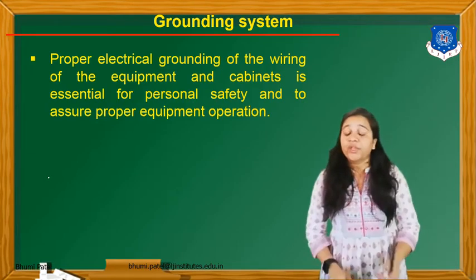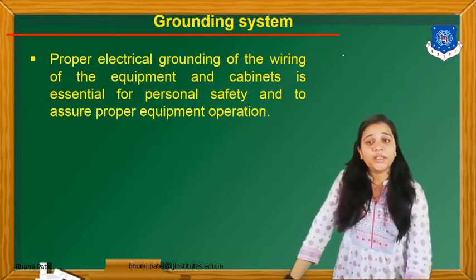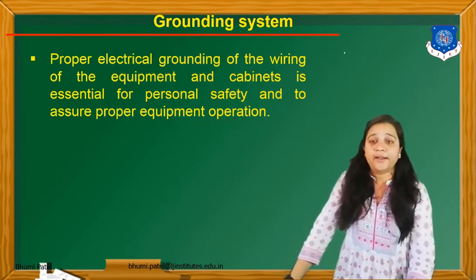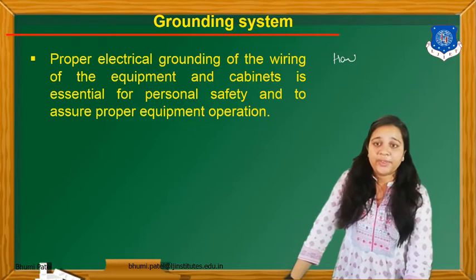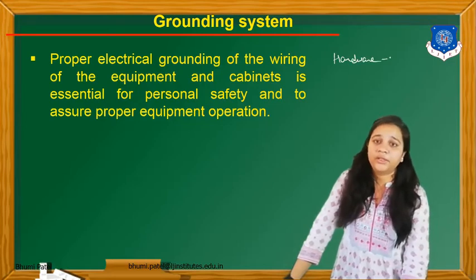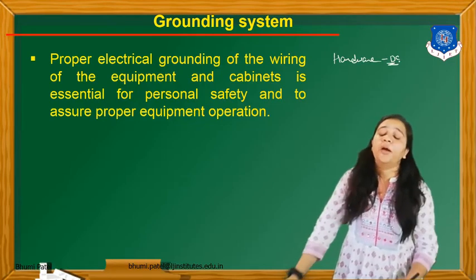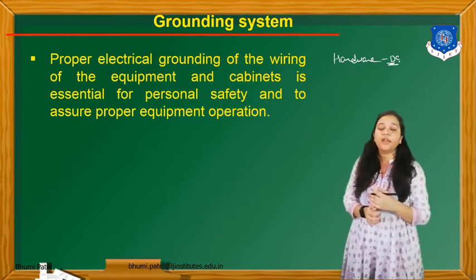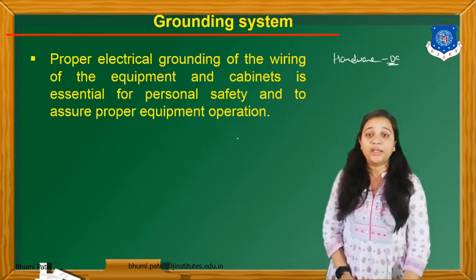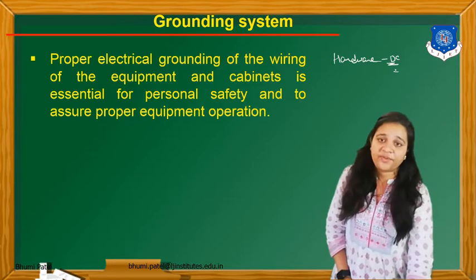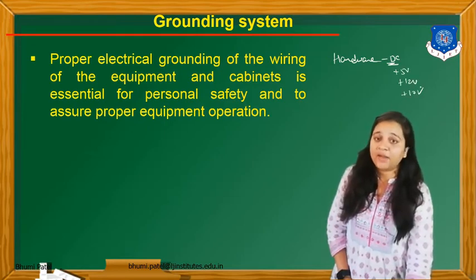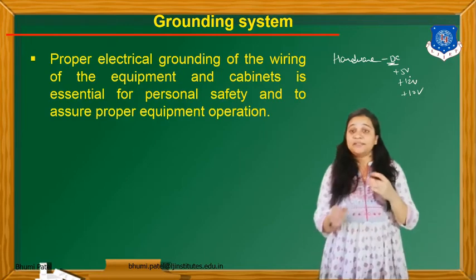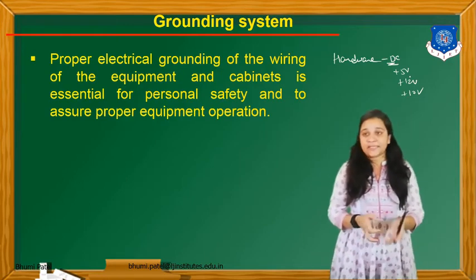As you know, in the PLC, if we only have to connect the PLC hardware, the PLC works on DC supply. Depending on the manufacturer or different types of companies, PLC will work on plus 5 volt DC supply, plus 12 volt DC supply, or plus 10 volt DC supply. This is the power for only the PLC hardware.